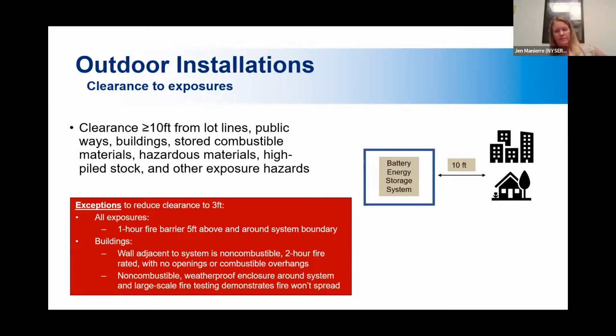And this is one of those instances where the clearance can be reduced to 3 feet by the fire code official if you do certain things. So if you put a 1 hour fire barrier all around that system, you could reduce the clearance to 3 feet instead of 10. I won't go through every single exception here, but I think the point of this is to illustrate some of the other exceptions that you might see throughout the code.